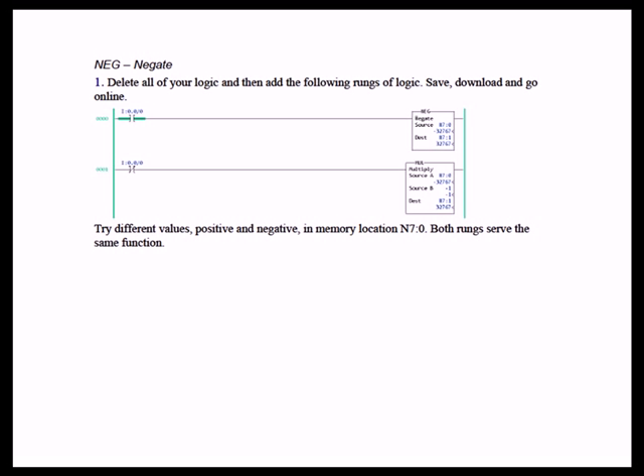However, I will say that rung 0 takes less memory space and probably executes a little faster than rung 1. And I think the instruction is fairly straightforward, the negate instruction. If anybody is troubleshooting and they come across a negate instruction, they are going to see that the source is N70 and the destination is N71. And what is in N71 is basically the result of N70 multiplied by negative 1.